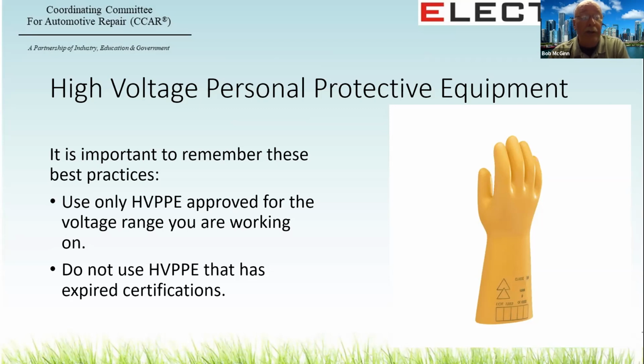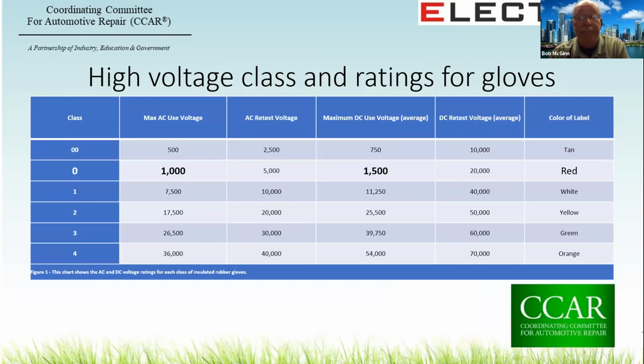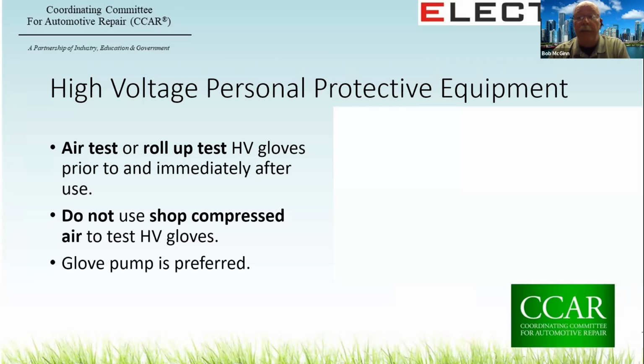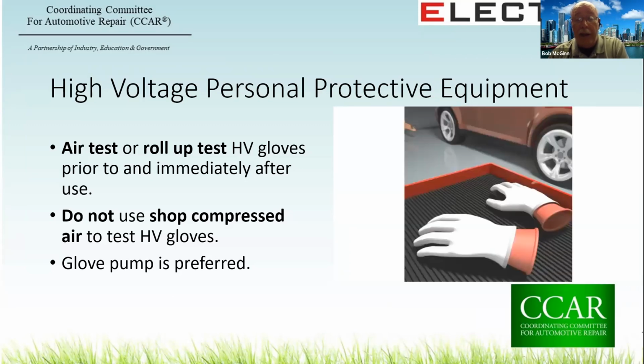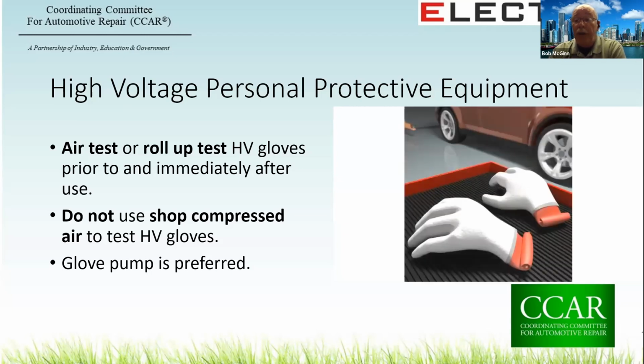We do not use expired PPE. Class 0 is your target group for rubber gloves or any other rubber items, and that tag on that item is red. Now, rubber gloves need to be inspected for surface defects. Air testing is a standard test for integrity by either a roll-up test or using a glove pump. No shop air at any time.